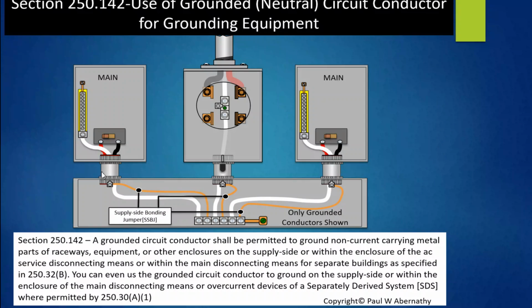Well, we had the same situation. We're using concentric or eccentric knockouts. It's probably the standard. And so I have to bond this raceway here. Now, because of those knockouts, I have to use a bonding bushing with a bonding jumper. And it is sized based on the size of the conductors that are supplying this raceway. Okay? And over here, the same thing.